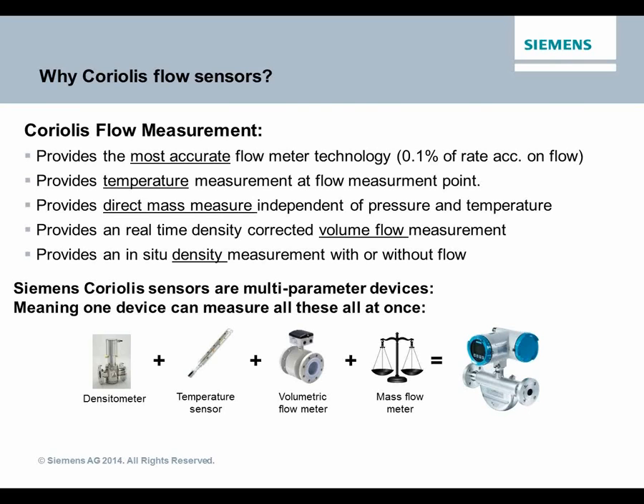Finally, since you have density, you can also calculate volumetric flow. So if your application, process, or recipe requires an actual volumetric measurement as opposed to a mass flow measurement, the Coriolis mass flow meter is a very good volumetric flow meter as well. And it actually provides real-time volumetric measurement because you're getting the mass divided by the density in real time. So there are no fixed values. So your values are very representative of your actual flow.